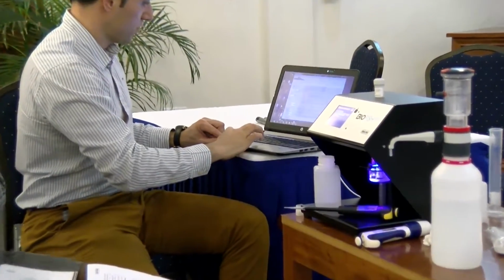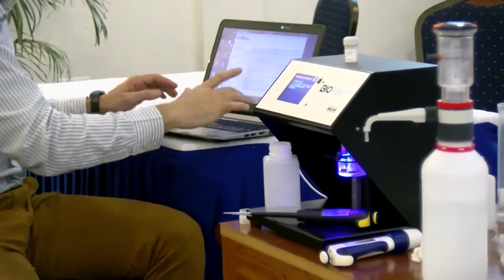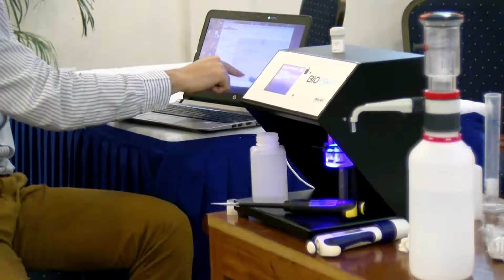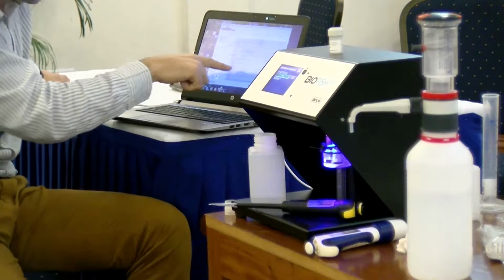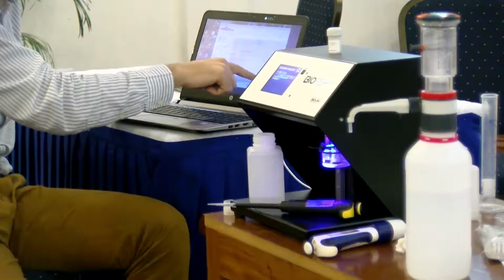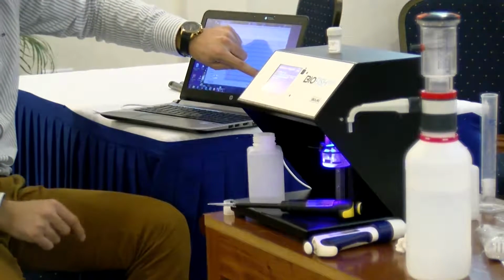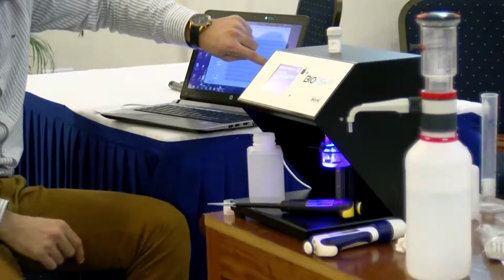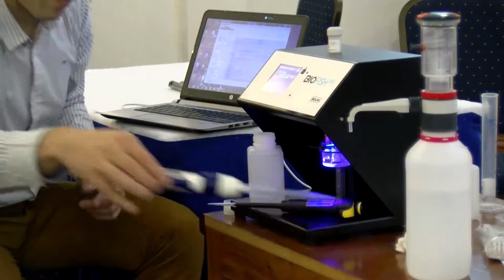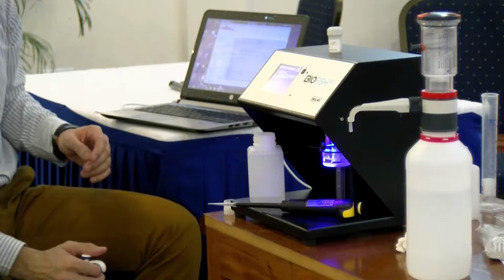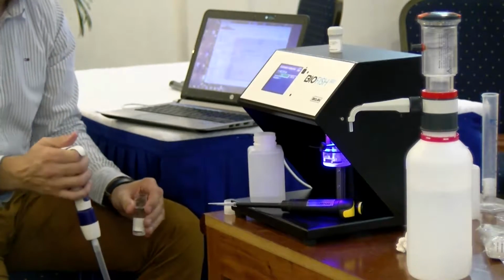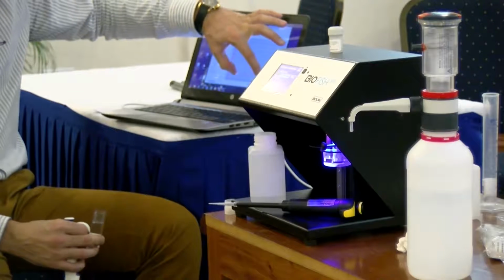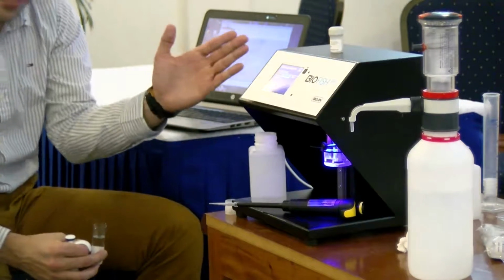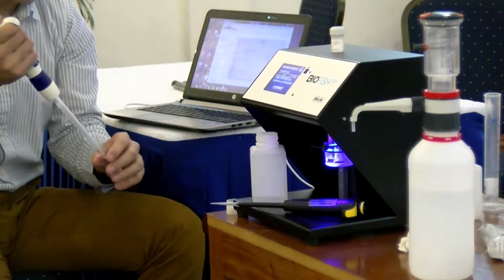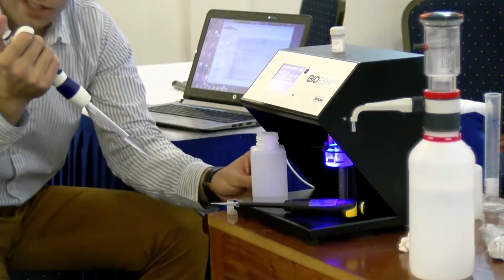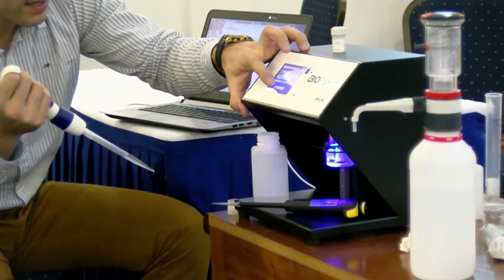Now I'm going to zoom in here. Look. This is the reason why the device has wasted time, because the current signal is not very stable. Well, you see, in this moment we made the addition. There is a jump. Probably this electrical noise is due to the fact that we did not carry out the first stage of activation that we skipped, to make it quicker.